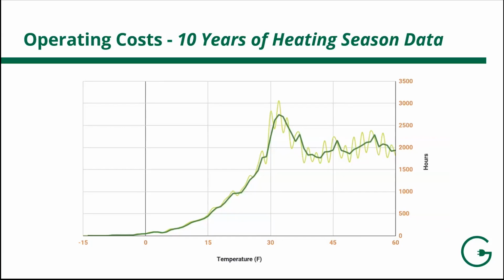When transitioning to heat pumps, your electric usage will increase, while your gas, oil, or propane usage will be reduced. To compare heating costs, there are three things to look at: weather, the efficiency of the equipment, and fuel costs. Looking first at weather, this is 10 years of heating season data from New England. The x-axis shows the temperature and the y-axis shows the hour of the heating season at that temperature. As you can see, we have roughly 2,000 hours at 60 degrees and roughly 2,500 hours at 32 degrees. So the majority of the winter you're in that 30 to 60 degree range, and 20 to 30% of the winter you're in colder temperatures.